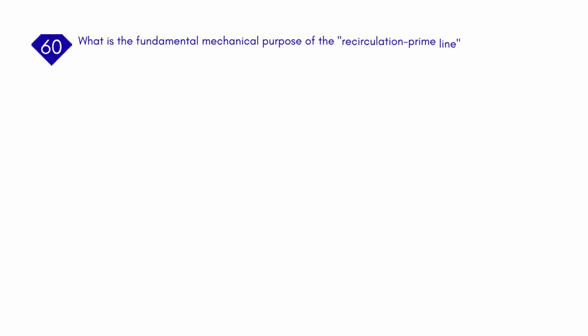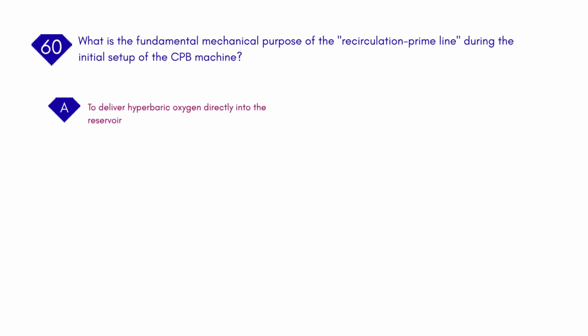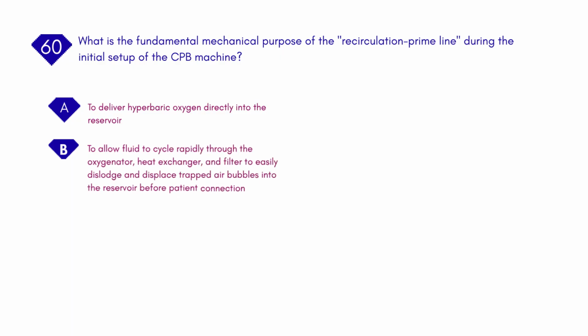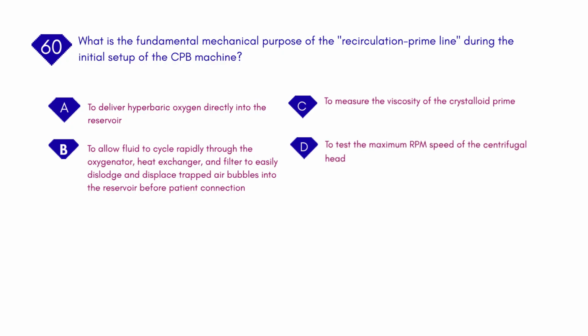What is the fundamental mechanical purpose of the recirculation prime line during the initial setup of the CPB machine? A. To deliver hyperbaric oxygen directly into the reservoir. B. To allow fluid to cycle rapidly through the oxygenator, heat exchanger, and filter to easily dislodge and displace trapped air bubbles into the reservoir before patient connection. C. To measure the viscosity of the crystalloid prime. D. To test the maximum RPM speed of the centrifugal head.